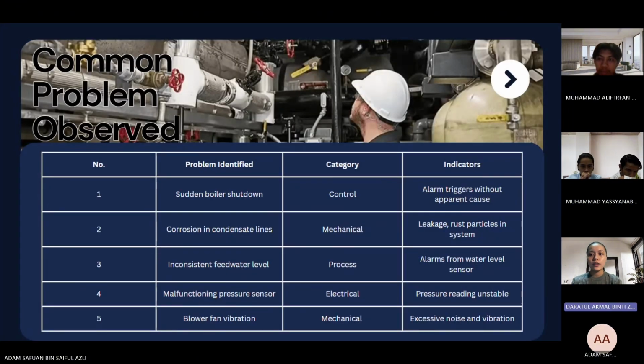Now let's take a look at the common problems we have identified in package boiler operation. The first one is sudden boiler shutdown. The category is control and the indicator for it is alarm triggers without apparent cause. The second one is corrosion in condensate line, which falls under mechanical issue. It can be detected through leakage or rust particles in the system. The third one is inconsistent feed water level, which is a process-related problem often caused by a faulty water level sensor.